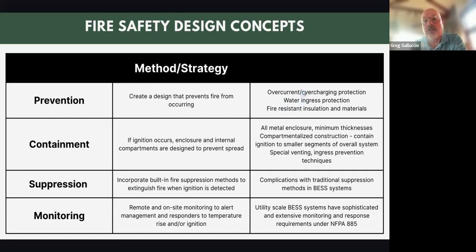Finally, fire-resistant insulation materials and enclosure designs prevent fires from starting. The second safeguard is containment. We do this for everything from hair dryers to toasters to electric vehicles—if the outer enclosure is designed to not allow fire to escape, it only harms the batteries themselves, or the vehicle if it's an EV, but nothing around it. That's called containment, and that's why BESS systems are housed in rather robust metal containers.